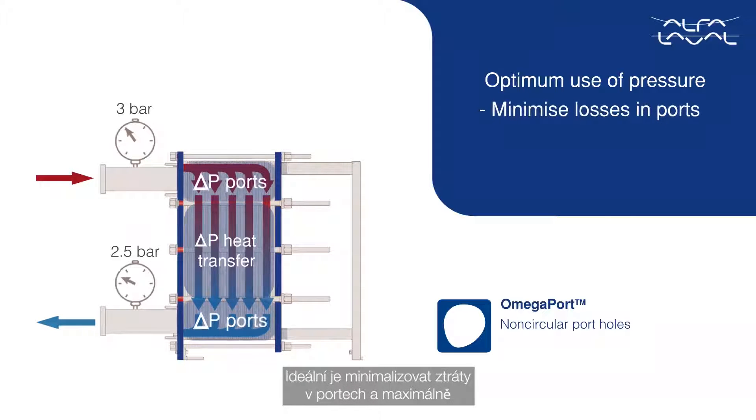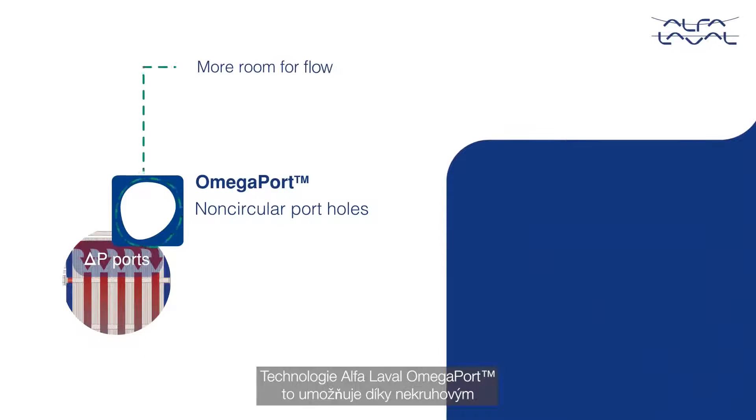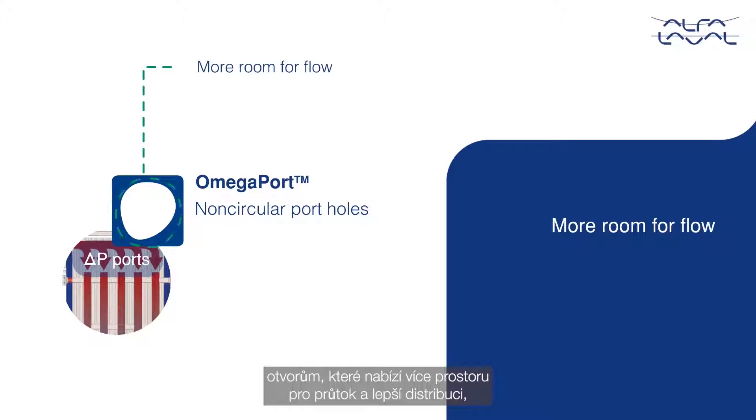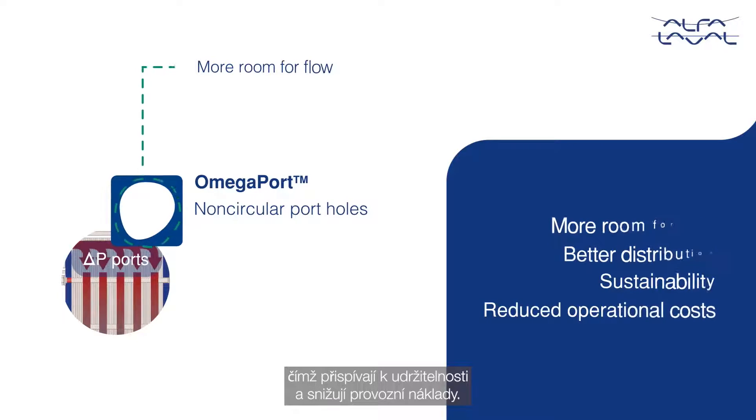The ideal is to minimize losses in ports and maximize the use of pressure in the channels for efficient heat transfer. The Alfa Laval OmegaPort technology enables this with non-circular port holes, providing more room for flow and a better distribution — hence contributing to sustainability with reduced operational costs.